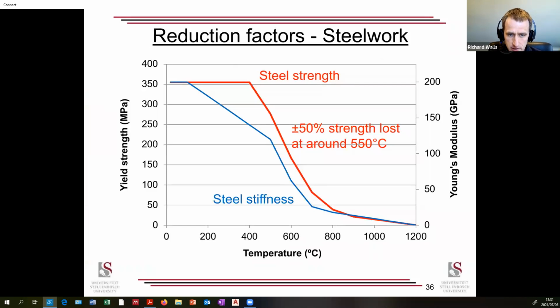So why do we put products on steel? It is to prevent the steel getting too weak. For instance, up to about 400 degrees Celsius, we've got almost all the steel strength, and then the strength drops quickly. So what we do is we try to limit the steel to a certain temperature, and you will sometimes hear a critical temperature of 500 or 450 or 600 being listed.